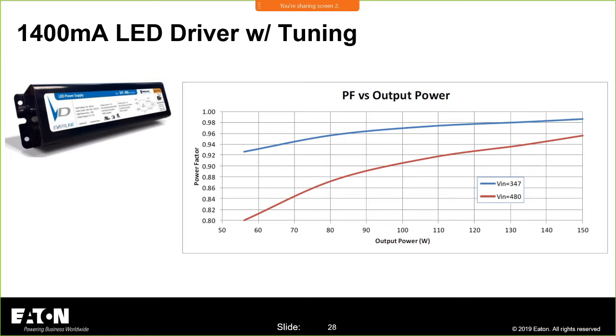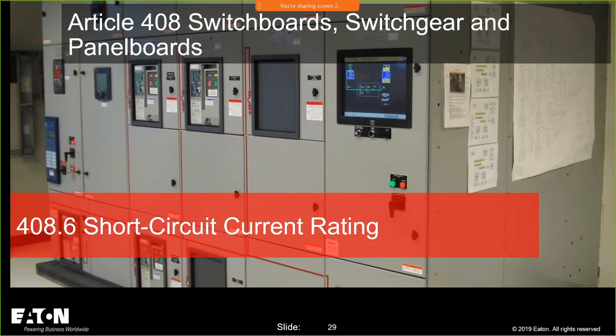but a lot of our lighting, you got to be careful. They always love to talk about watts per square foot. They love to talk about reducing that W. But especially if you're in an industrial, the utilities are going to charge you for VA as well. They're going to charge you for power factor, and you've got to think about the higher the power factor, the more efficient use of the energy that you're providing, and especially if you have a lot of these things that could save you money, spending a little bit more on these fixtures to make sure that you get the higher power factor. And I don't think you want to get into the practice of applying power factor correction locally.